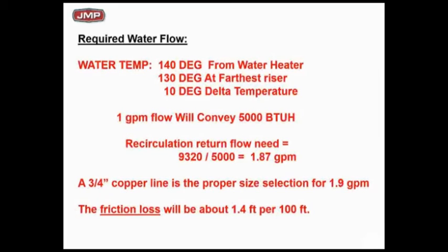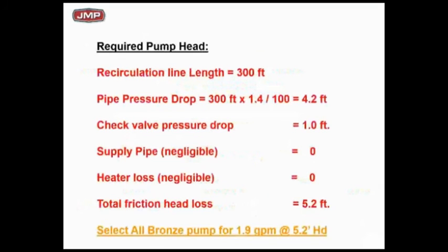Now if I use a 3/4-inch copper line for the hot water return, the friction at 2 GPM through that 3/4-inch pipe is 1.4 feet per 100 feet of pipe from the Bell & Gossett system sizing chart. Adding that all together — including a check valve, not worrying about the large supply pipe with only 2 GPM flowing, and not worrying about the water heater at 2 GPM — my total friction loss for the pump is 5.2 feet. To make a long story short, you need to pick a pump for 2 GPM at 5 feet of head. That's why 90% of the time this sizing exercise doesn't take long.